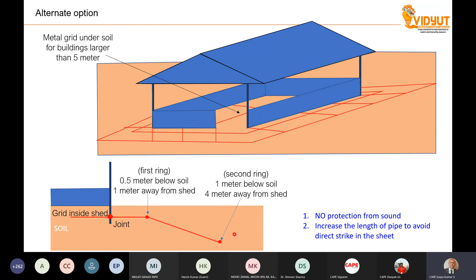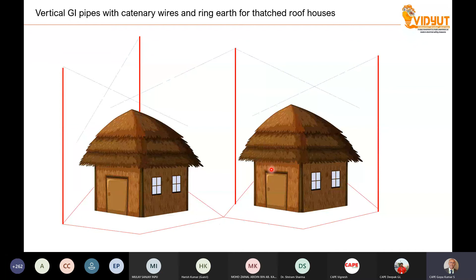So if you want to protect buildings with thatch roofs, you can have one GI pipe, a commercially available, locally available GI pipe. If you use an MS pipe, probably the life is less. If you use a GI pipe, the life is probably a little bit more. You can find out the area of protection by the angle method, or you can also have a catenary wire interconnecting these rods. As a result, the buildings are protected. But don't forget to put the ring conductor.